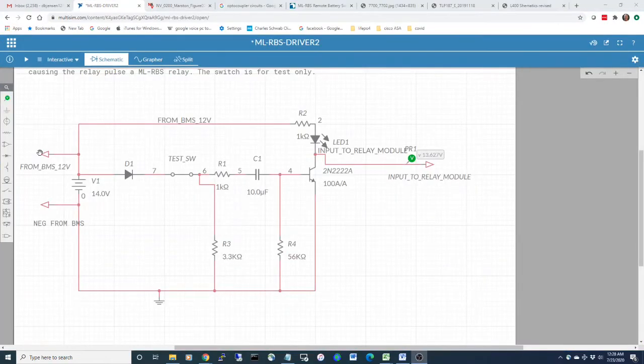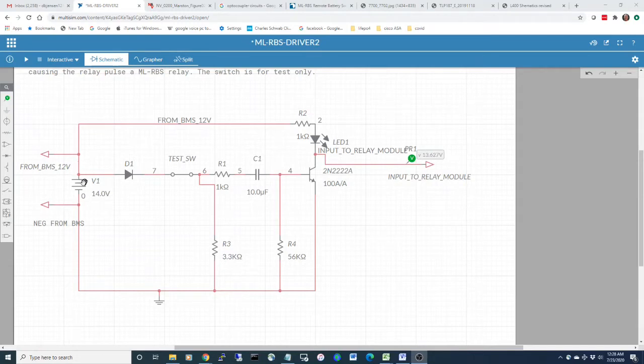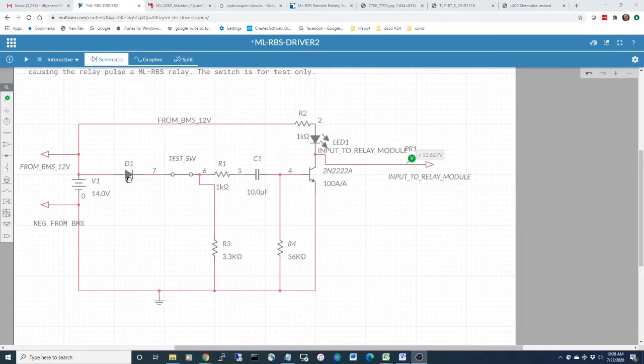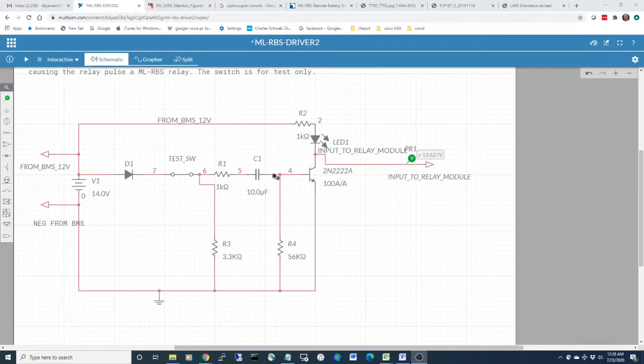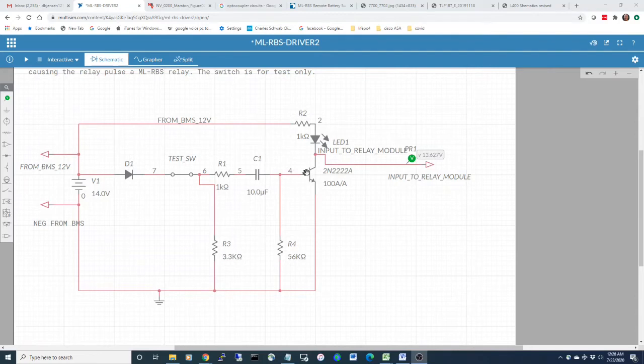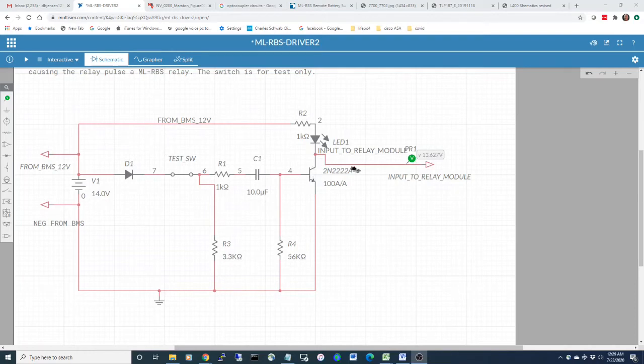What we're going to have is a signal coming from the BMS, the opto-isolator, a relay. We're going to go into a diode that's going to create some sort of reverse voltage protection, and then we're going to hit this capacitor here that's going to be a timing capacitor - that's what's going to provide the length of time that this pulse is going to last. That pulse will cause this transistor to close, and that closure will cause the pulse to go over to the relay module. The rest of these resistors are mainly pull-down resistors.